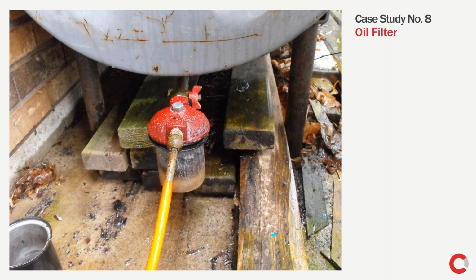In oil installations, you have water that accumulates due to condensation. Because water is heavier than oil, it always stays at the bottom of the tank. When the oil is running through the furnace, the first thing to draw out from the tank is water, and it accumulates inside the oil filter. The manufacturer requirements are to change the filter at the onset of cold season, and when there is water accumulated, evacuate it.